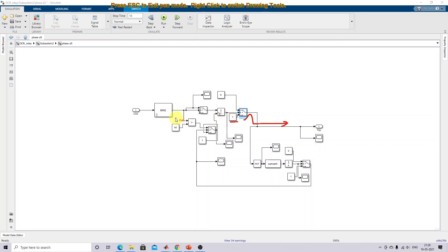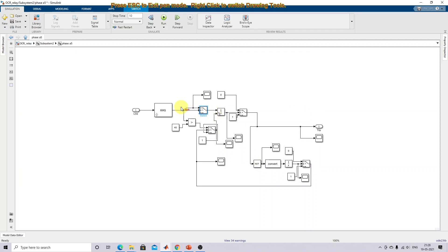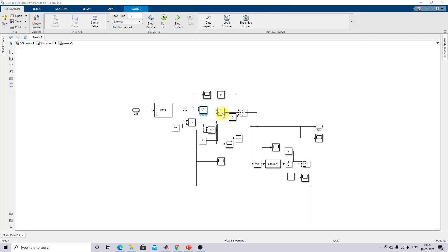If a fault occurs in the system — for example, a three-phase to ground fault — the current limit will go beyond 40 amps, so the condition becomes true. The same current flows through the integrator. Because of integration, it will take some time to reach the value. After the integrator output also reaches above the overcurrent setting, the condition will be true, and it will allow a zero signal to open the circuit breaker. This is the working of this overcurrent relay.